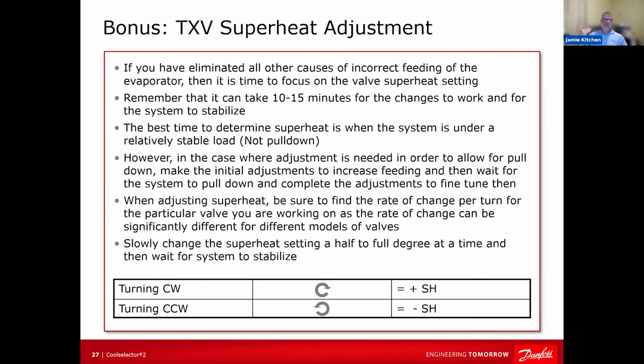You reverse it, you lower the superheat, and the valve is going to start to open. Now, remember that point where I talked about the class that understood what happened when the TXV opened up, but they didn't really understand the rest of the system from a system standpoint? That's what you're basically doing. If you open the TXV or close it by decreasing or increasing the superheat, it takes time for it to work its way around. You will immediately see a change in the evaporator, instantaneous.